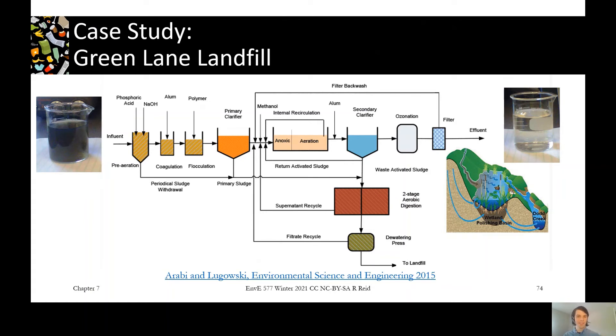Next, we're going into an activated sludge process. It's split up with an anoxic and aerated zone to get some denitrification going on and also to enhance that denitrification, we're adding methanol into the system. So that's an additional carbon source to help with the denitrification process. And you also see that with domestic wastewater treatment. That's sometimes something that you need to add.